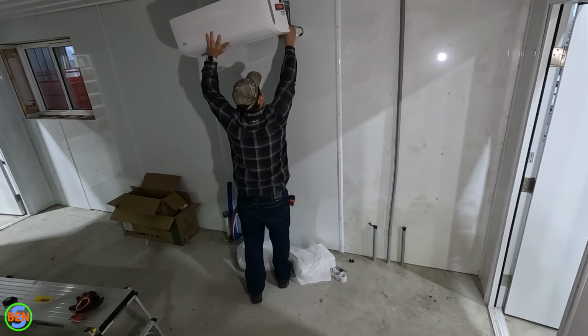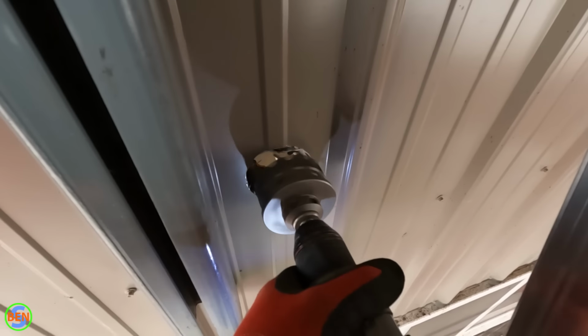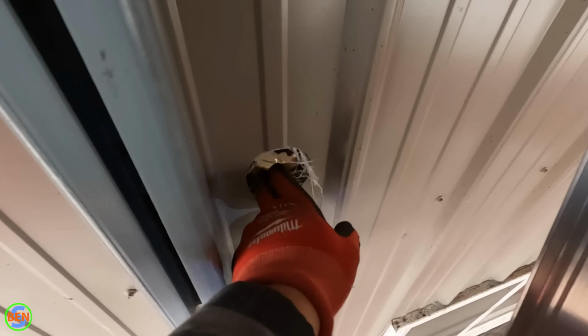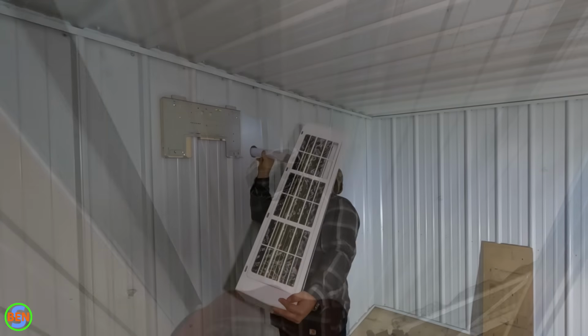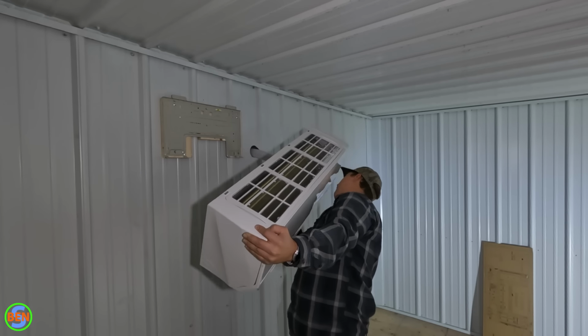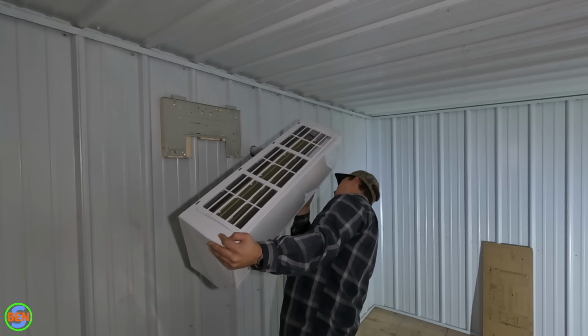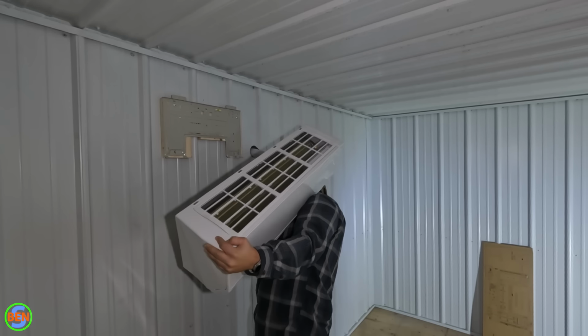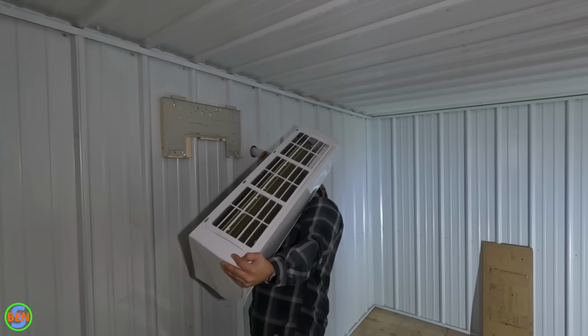And that 50-foot line set was going over to the 9K unit in that more remote room. The second wall hung unit was kind of interesting in that it is directly on the other side of where the outdoor mini split unit was mounted. And the interesting thing about that is that we could have gotten by with as little as 4 feet of line set, which at first sounds good, but actually that is not a good thing to do.